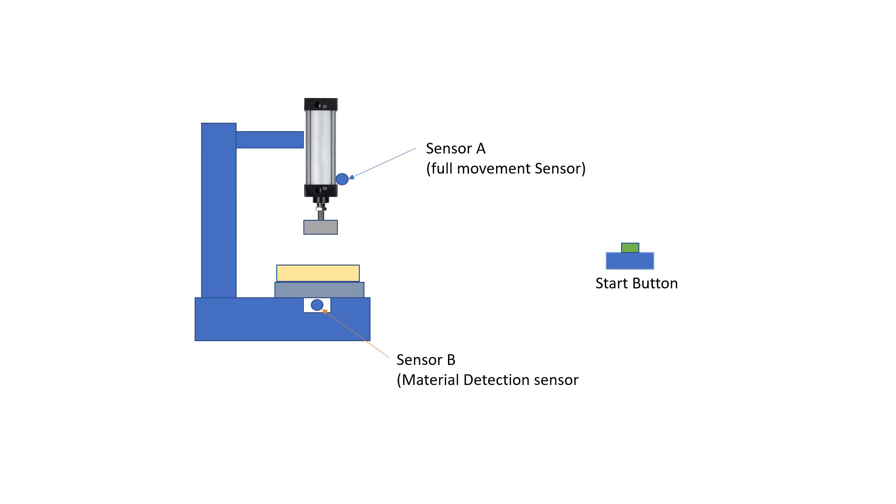When sensor A detects that the piston has fully moved, it will then start a timer which will delay for five seconds, putting the pressure on the material for five seconds. After five seconds it needs to de-energize and move back to its original position.